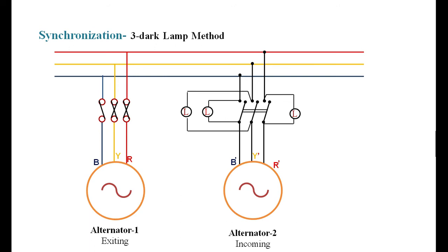One by one you have to fulfill each condition. The first condition is that the voltage of the incoming machine must be the same as the bus bar voltage. To test this, connect a voltmeter to measure the bus bar voltage, then adjust the field of the alternator such that the generated voltage equals the bus bar voltage.